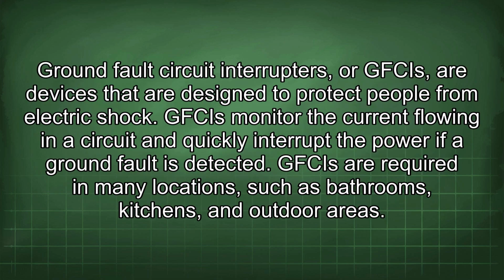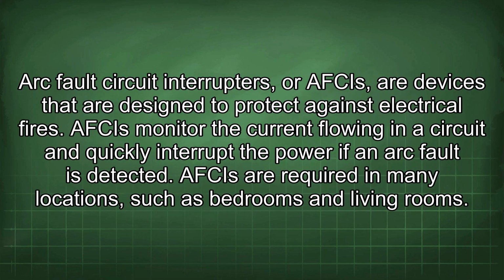Ground fault circuit interrupters, or GFCIs, are devices that are designed to protect people from electric shock. GFCIs monitor the current flowing in a circuit and quickly interrupt the power if a ground fault is detected. GFCIs are required in many locations, such as bathrooms, kitchens, and outdoor areas. Arc fault circuit interrupters, or AFCIs, are devices that are designed to protect against electrical fires. AFCIs monitor the current flowing in a circuit and quickly interrupt the power if an arc fault is detected. AFCIs are required in many locations, such as bedrooms and living rooms.